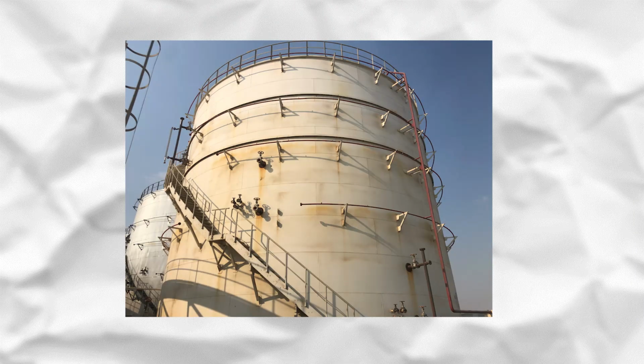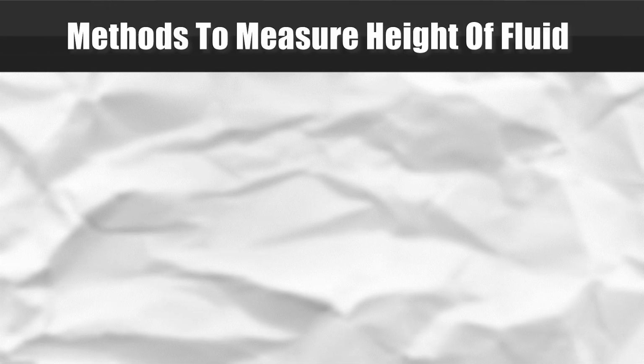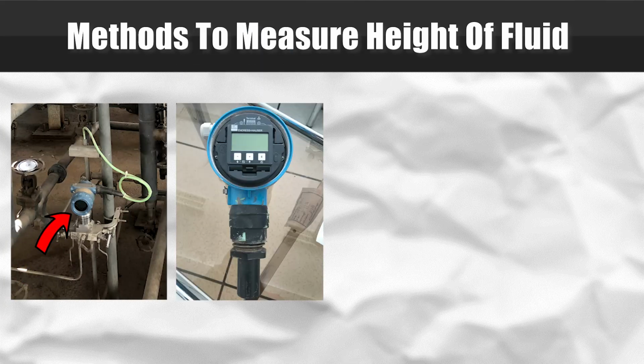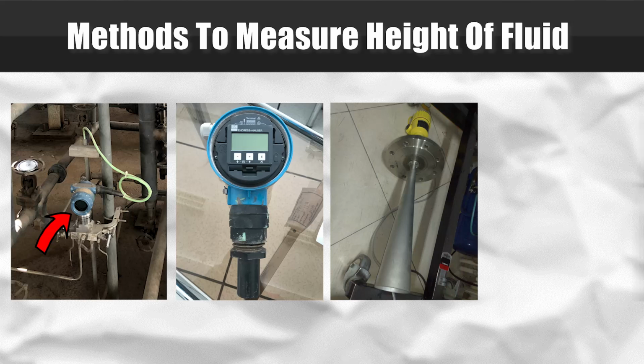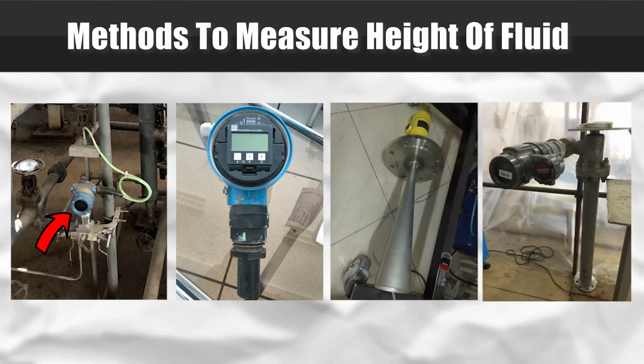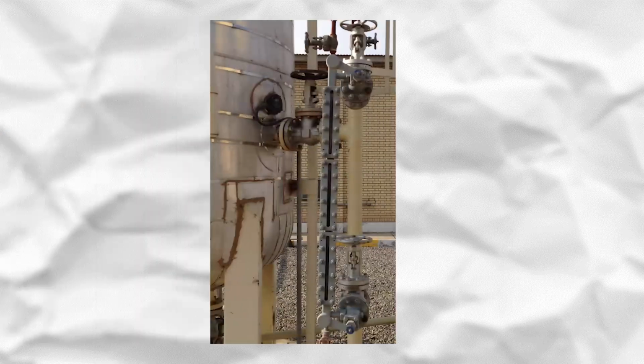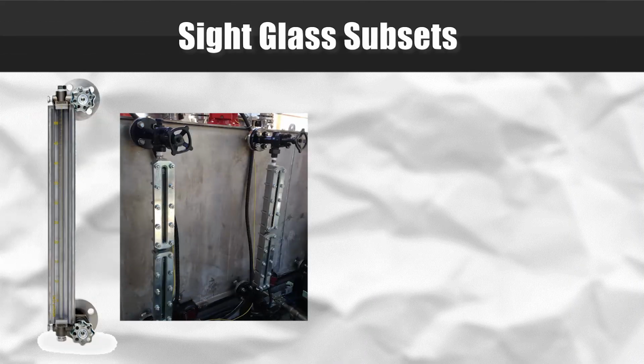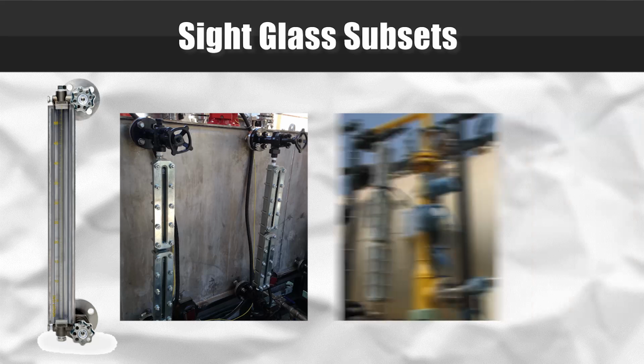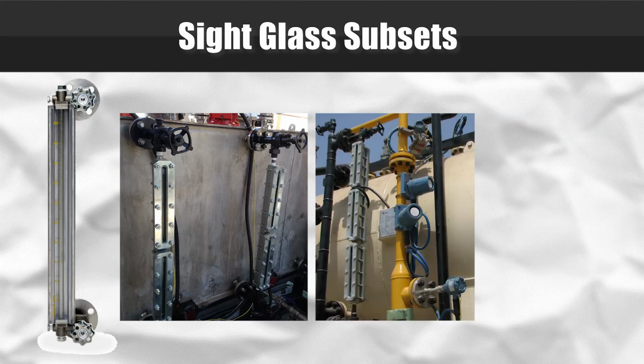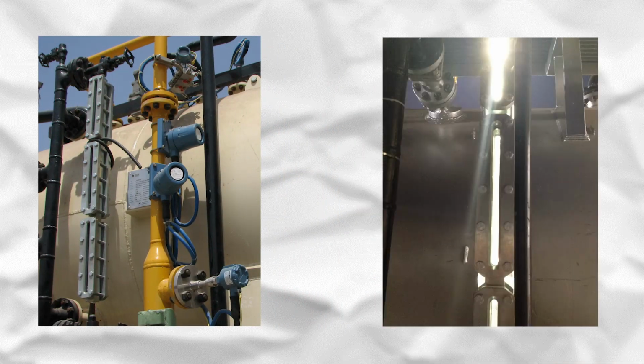Level measuring instruments are another part of this section, which are used to measure the height of fluid in a tank or a vessel. There are a variety of methods to measure this amount, such as differential pressure, ultrasonic waves, electromagnetic waves, and the buoyancy principle discovered by Archimedes in past centuries. As the simplest method, sight glasses would be used. Sight glass is categorized into 4 subsets: tubular, reflex, which is used for bright color fluid, transparent, which is used for dark color fluid, and magnetic type. You should be informed that the transparent type is equipped with an illuminator to be seen clearly at night.